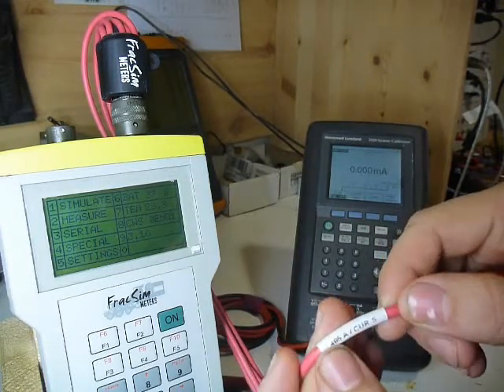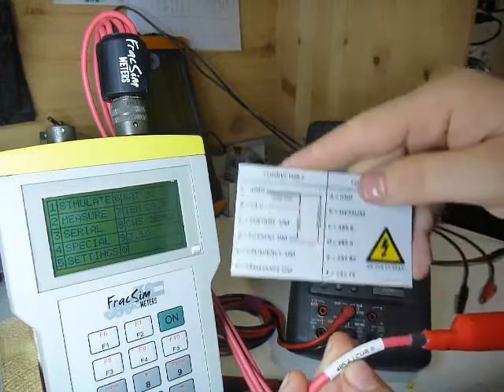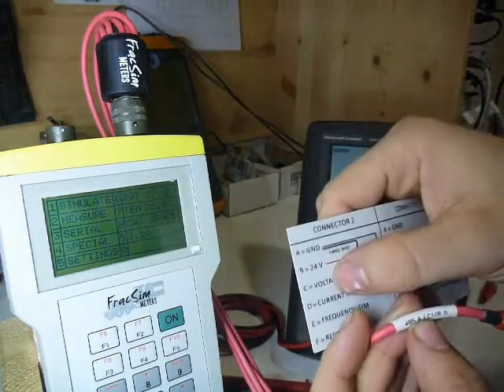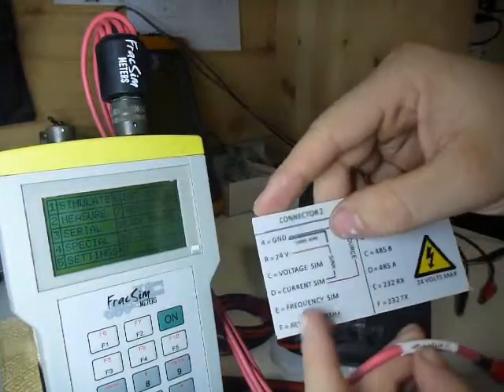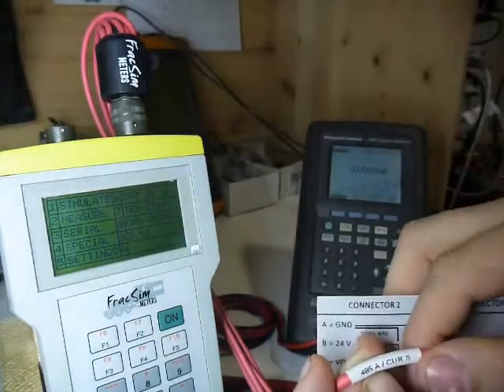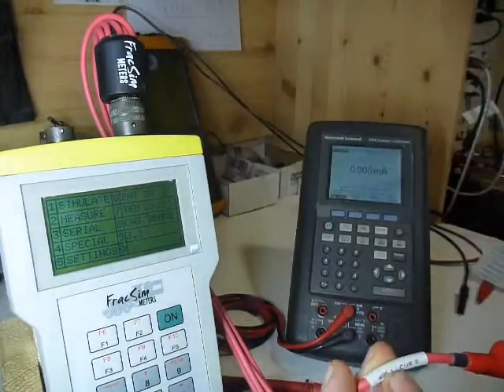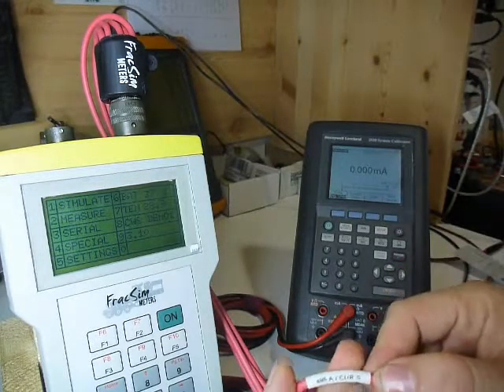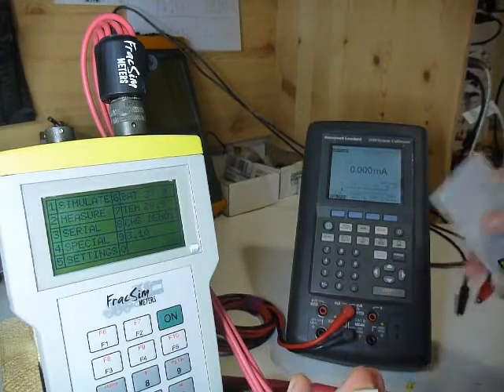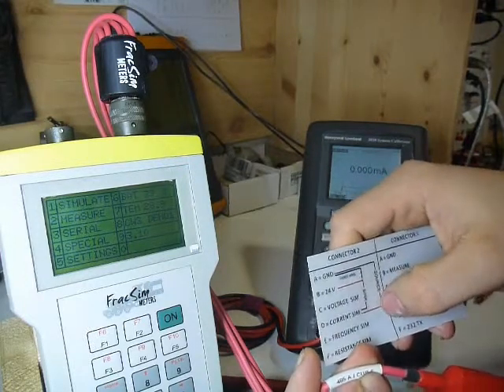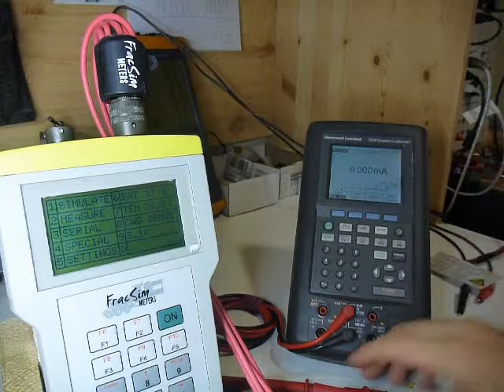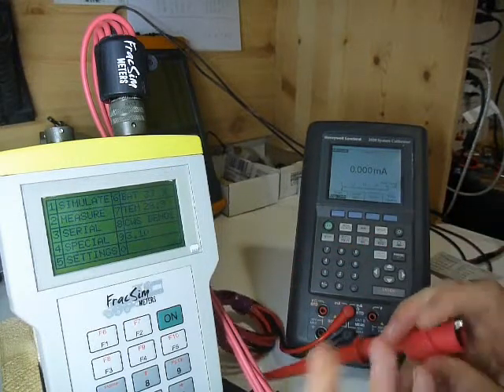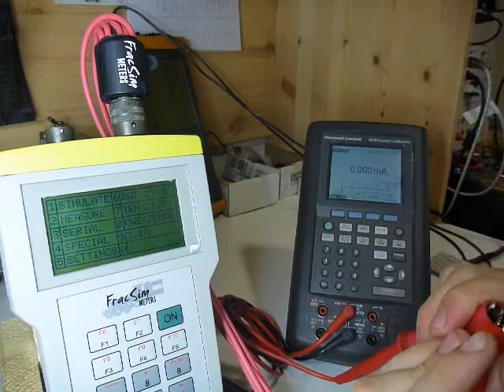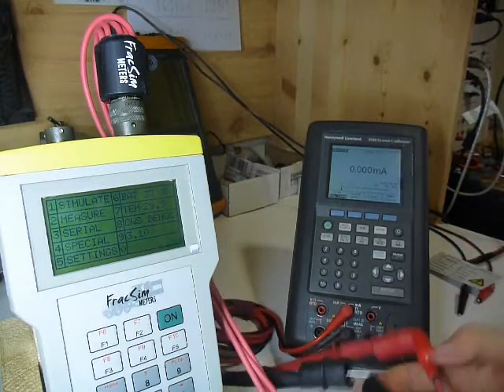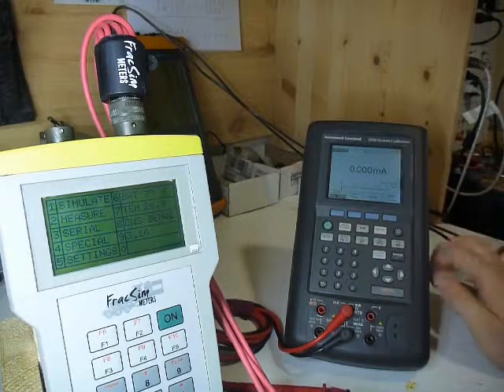Now, when you're looking at these leads, of course, they're double labeled for use on either side of the connector. So you see current sim is for use when you're on this side, and if you're on the other connector, of course, then it's going to be 485A, and that's how they're labeled here. So you can use this connector on either side. But for our application, current sim and ground. So current sim needs to go to the positive of what you're going to be sourcing into, and that happens to be the red lead on the 741 here, or equivalent. And the ground lead, of course, is the ground going on to the 741.